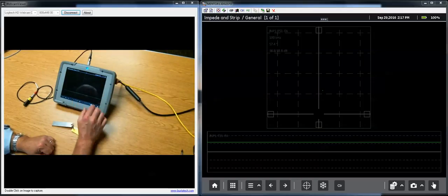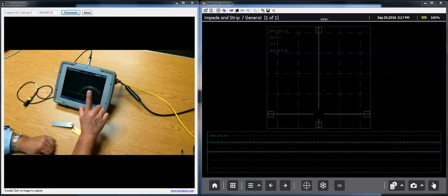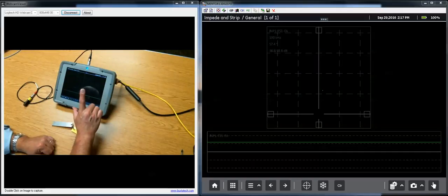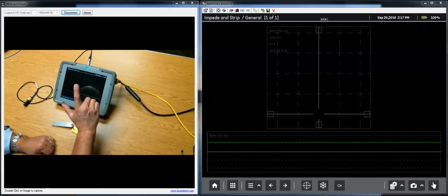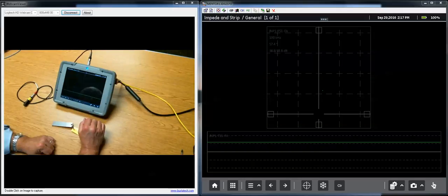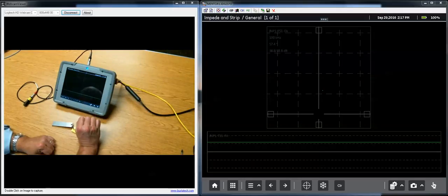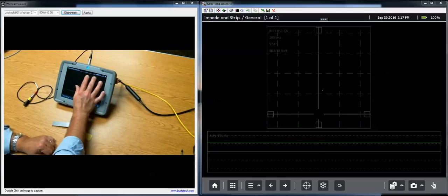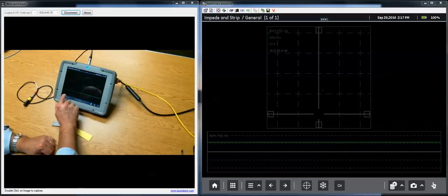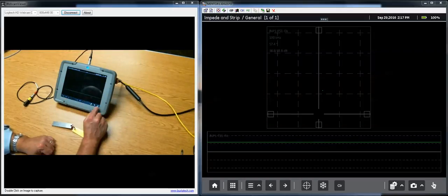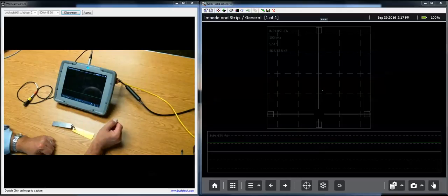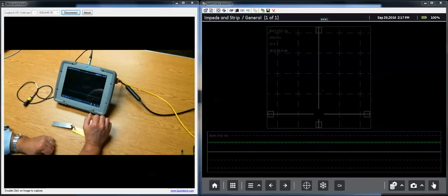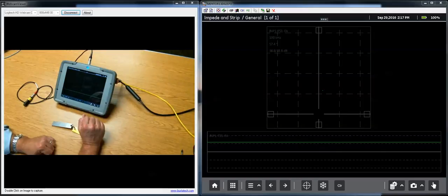With this little button down in the lower right hand corner, you see a finger icon. If you touch that, you notice now I have an X through the hand. Now it doesn't matter what I do here, nothing is going to respond on the touchscreen except that icon to unlock it again. So if your instrument ever stops responding and you wonder why, check down here and make sure that you haven't accidentally locked the touchscreen.